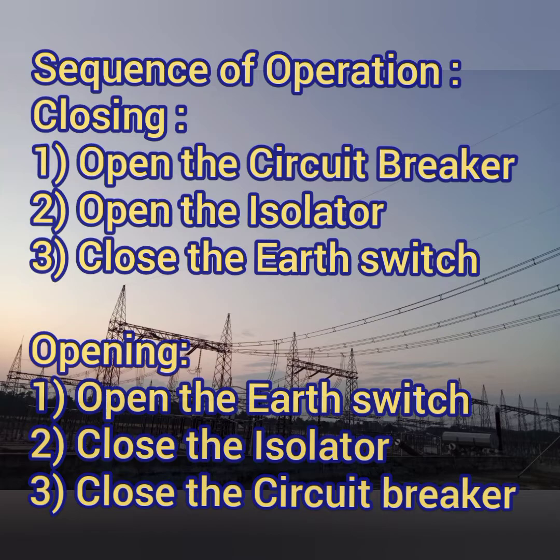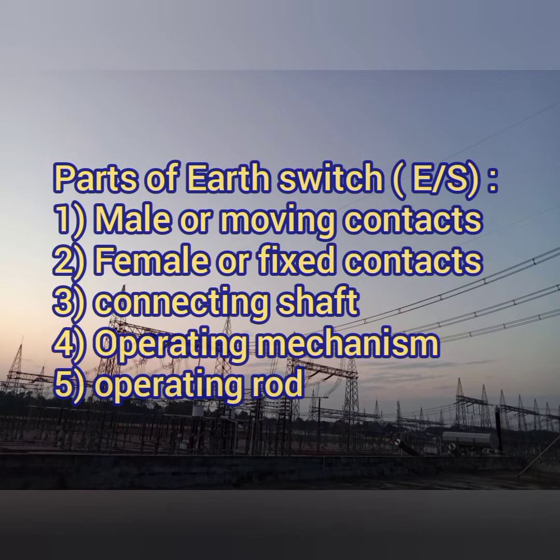The earth switch comprises main parts like male or moving contacts, then female or fixed contacts, then the connecting shafts which are used for operation, then rotating mechanisms or the operating mechanism for electrical operations, and the operating rod where the male contact is fixed. This earth switch has certain rating capacities for withstanding current and short circuit withstanding current, and is provided according to the voltage level or voltage rating.